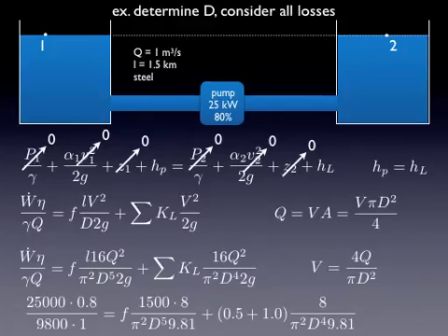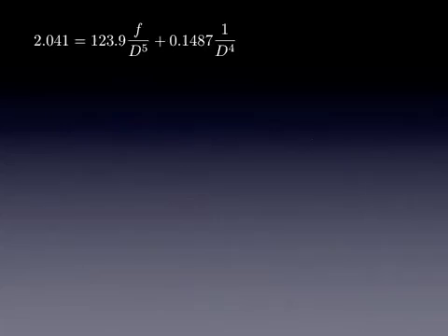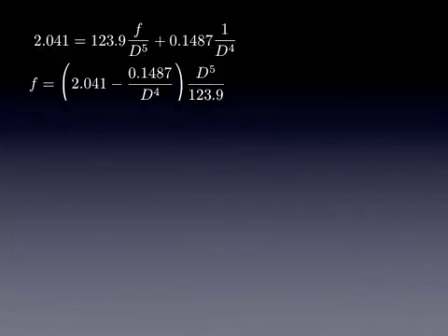I can plug in all the numbers that I know. So, we know we have information about the head, about the pump, and the efficiency of the pump, length of pipe, flow rate, the minor head losses. There are two minor head losses. There's an entrance and an exit that have coefficients of 0.5 and 1, and we can then reduce that and simplify, and we end up with this equation. I'm going to take it one more step and solve for F. Notice, in this form of the energy equation, it wouldn't be useful to guess an F, right? Because then you have to solve for D, and that's kind of a nightmare.